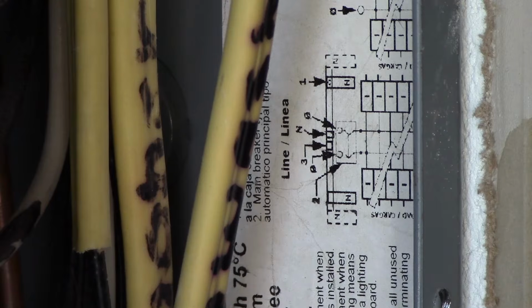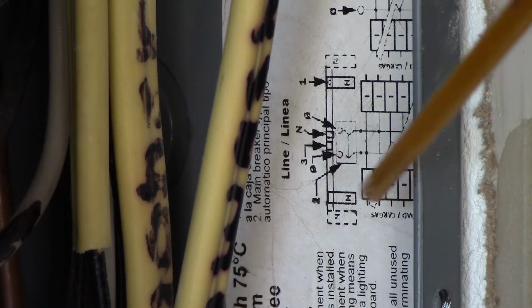Now, in any case, if you can't identify it or you can't really tell because of some of the complexities of some of these panel boards, don't be afraid to defer it, because we need to make sure of anything. We need to make sure that in a service panel, we have that main bonding jumper. And it might be a screw. It might be a Z-bar that connects from the bus over to the enclosure. Okay, it might be a wire from the bus over to the enclosure. It could be in different ways, but you need to make sure that it's there. And in this case, it has a green screw, so we know that's the main bonding jumper. All right, so that's the information.